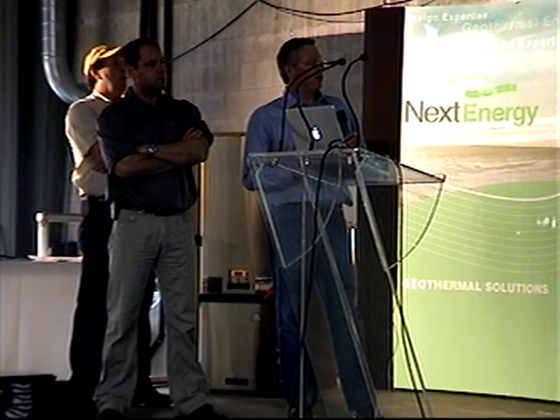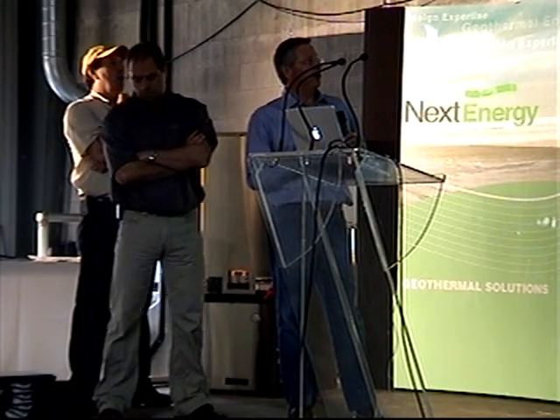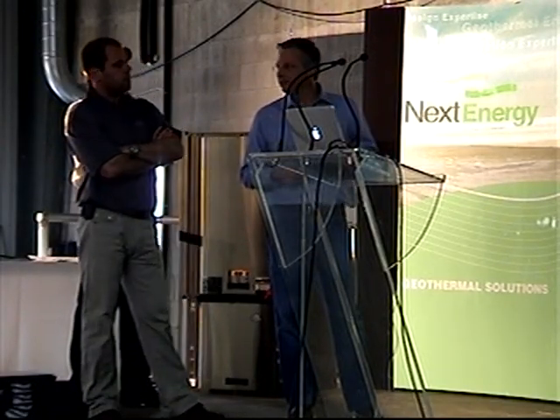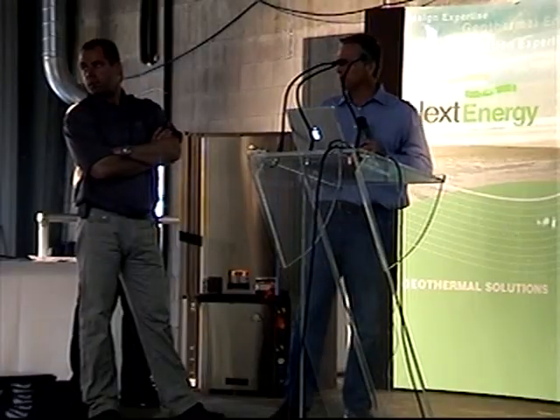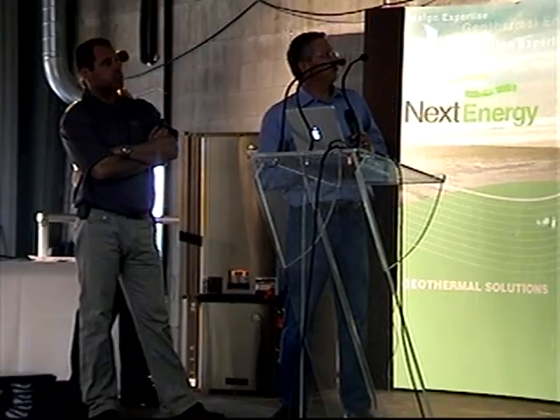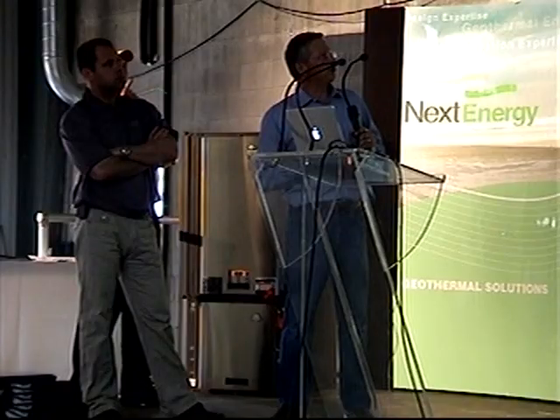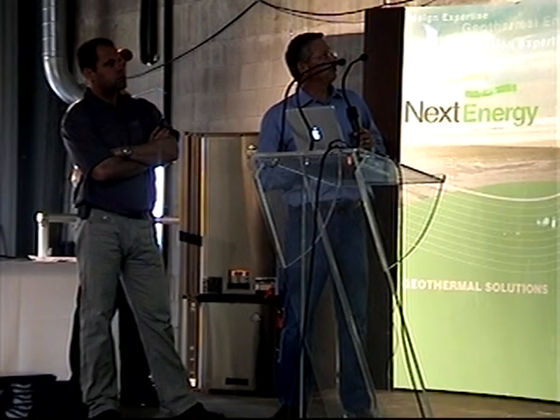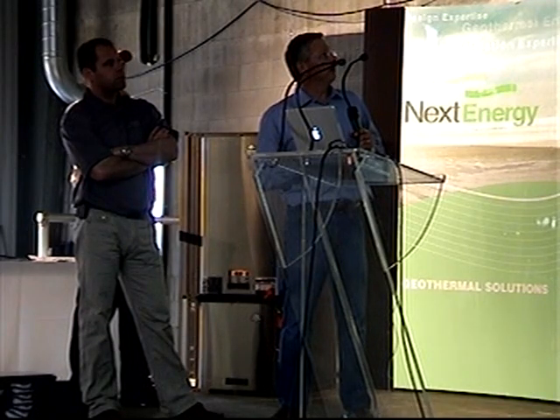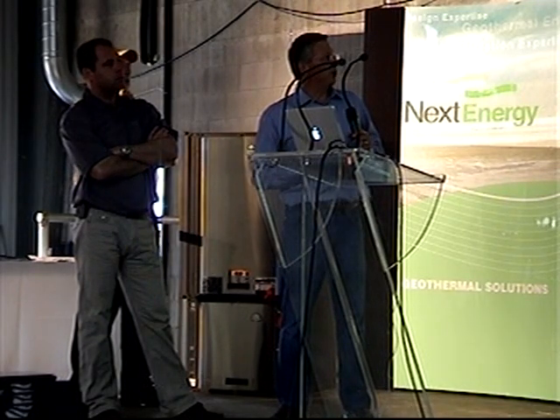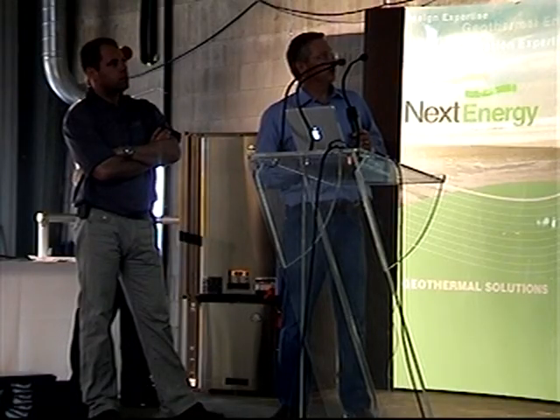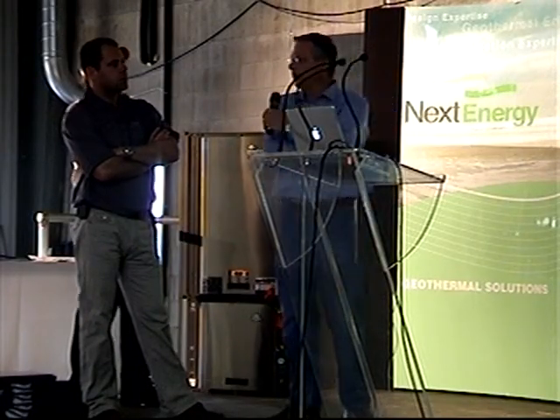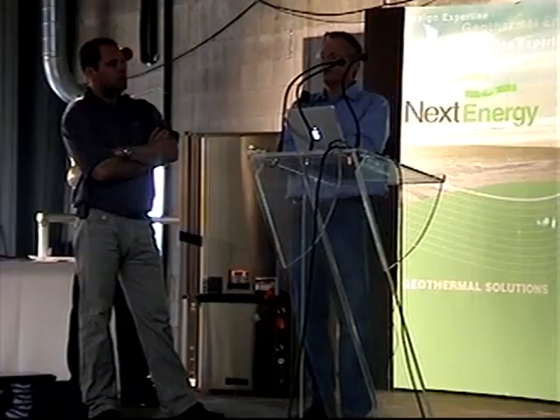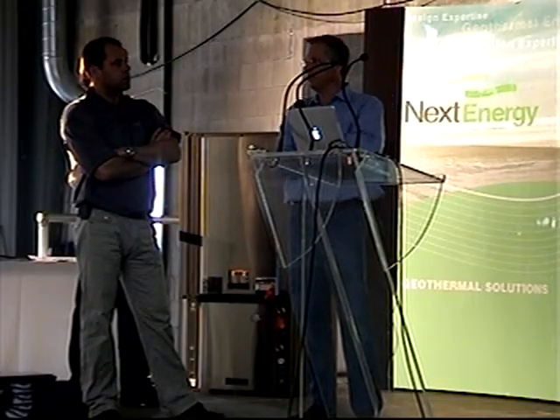It has fault retry automatically, so if it trips out on any of these things, it'll try again on its own. Different ones are different. I know high pressure it'll try, loss of charge it'll try, it'll check. I mean, it won't even start there. Condensate it would probably try. The only one is water coil freeze protection. I think we build in some stuff, and hopefully it'll be coming up in here. We made some changes to that.